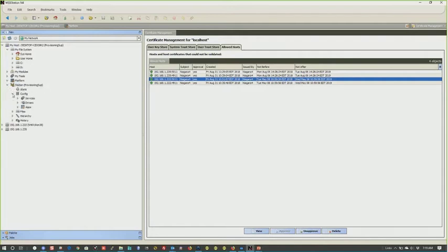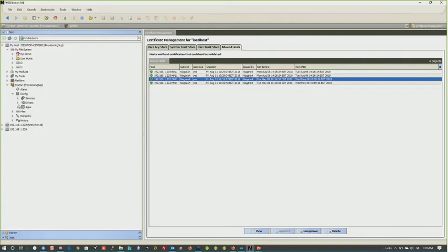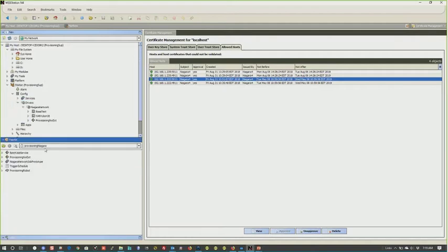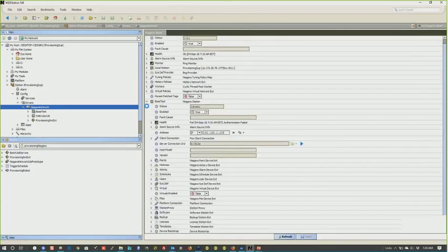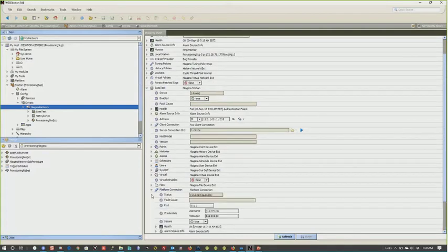So if we go in and look at our Niagara network, well, first we'll go to services. I have added the batch job service there, and then underneath the Niagara network, if I bring my palettes up here, which will make it easier, there's a provisioning Niagara palette that you use, and you drop the provisioning extension directly on your Niagara network. When you do that, if I go here and look at our JACEs, you'll see they have this platform connection, which only shows up if you have that provisioning extension installed. In there, you're going to give the platform credentials, and whether it's using secure Fox or a secure connection to the platform.